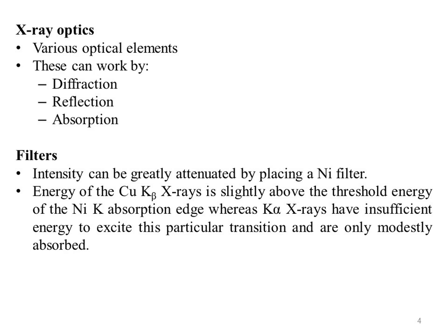For powder diffraction experiments using a laboratory source, diffraction of the copper K beta radiation contaminates the powder pattern from copper K alpha. Its intensity can be greatly attenuated by placing a nickel filter, a uniform thin sheet of nickel, in the beam path.